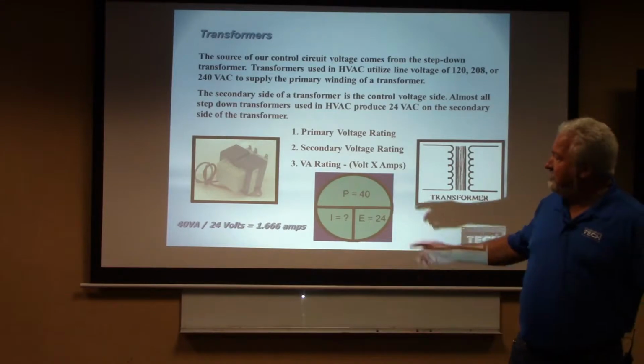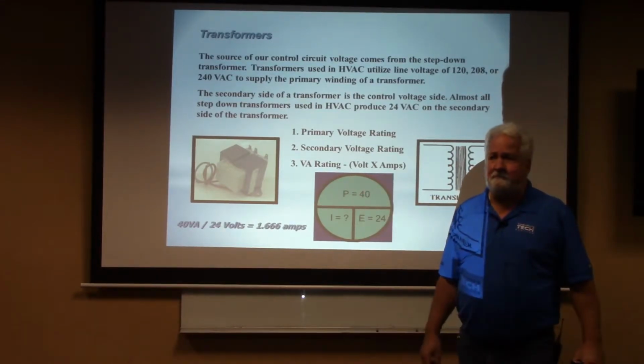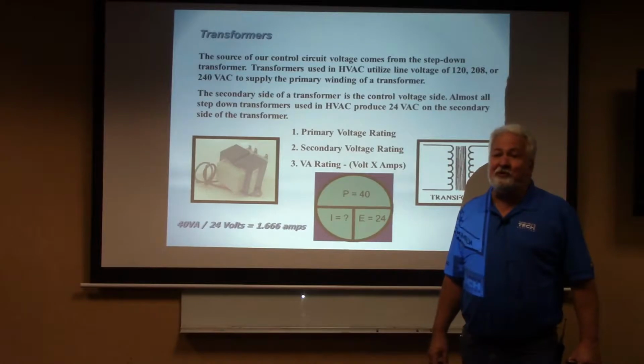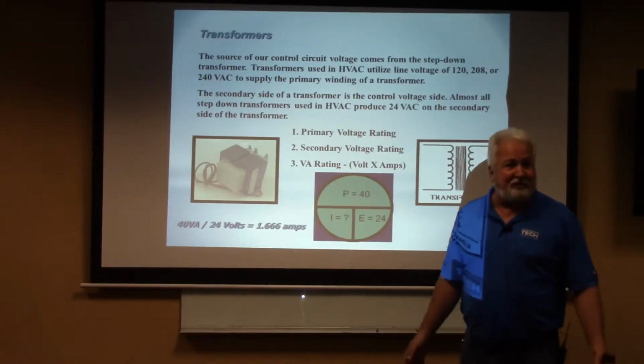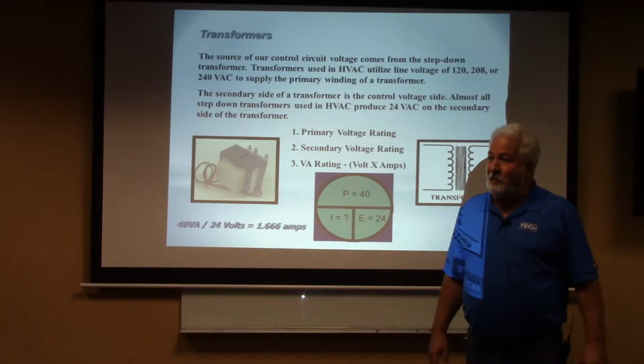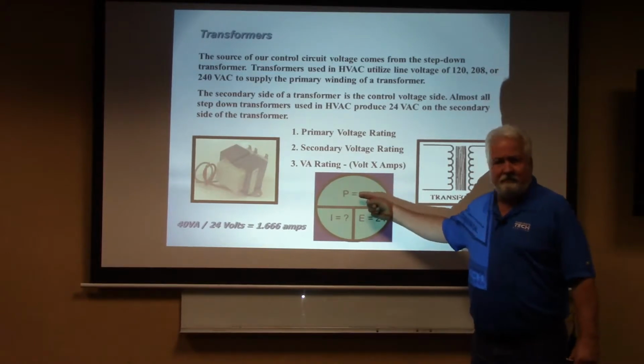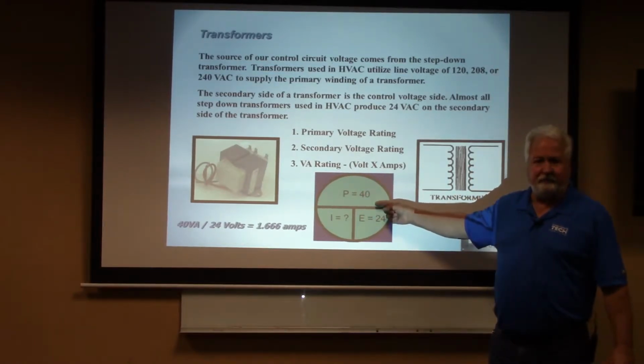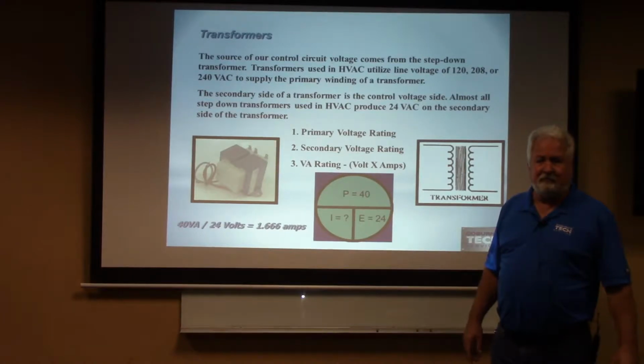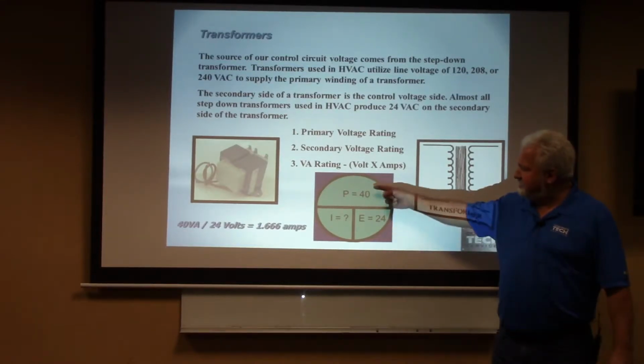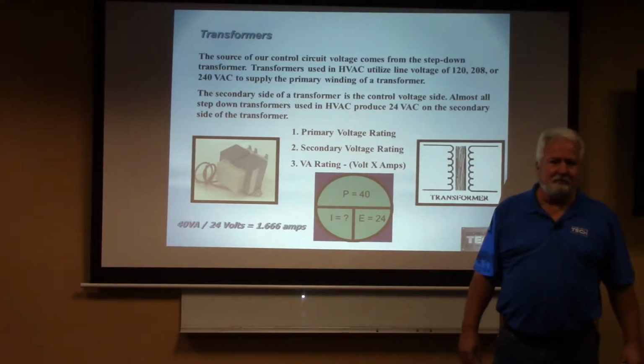If you measured 2 amps, is this 40 VA transformer going to work? So what would be the next? What do we always do? We just throw in a bigger one and then see if that one smokes, and we throw in another bigger one and see if that one smokes. Is that right? What if I put in a 50 VA transformer? 50 divided by 24 is 2.08. You're drawing 2 amps now. You're going to be safe with the 50, or what are you going to do? Go up to a 60. 60 divided by 24.